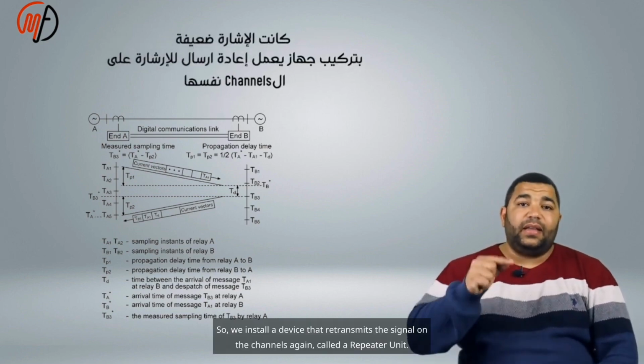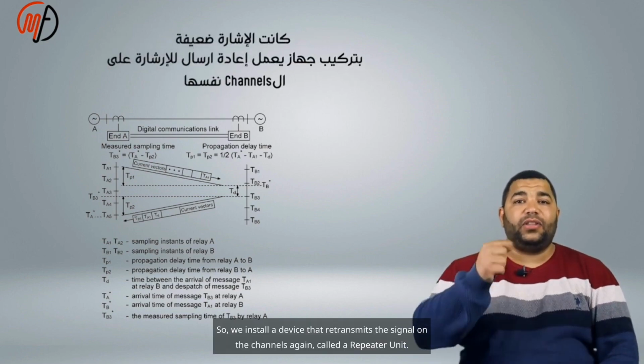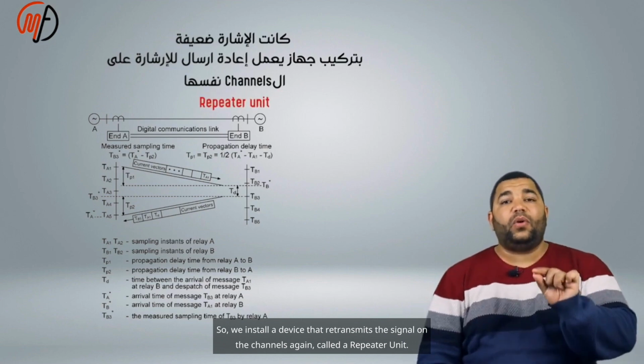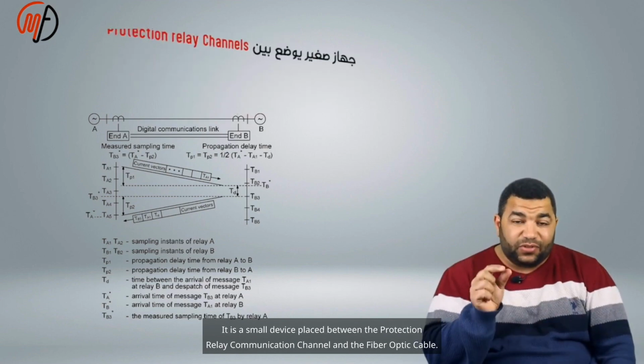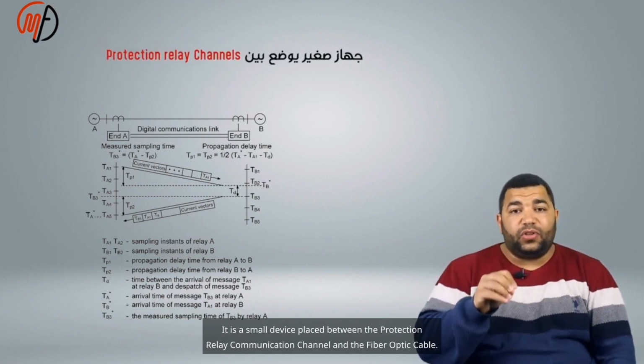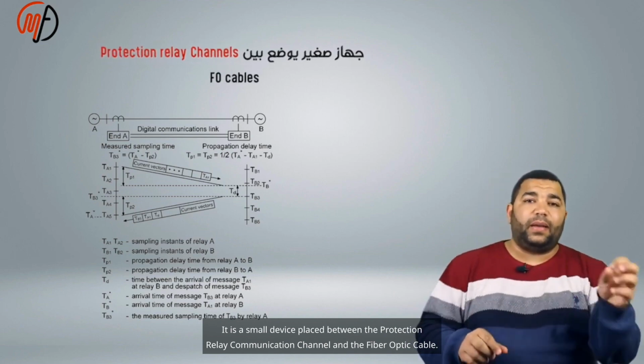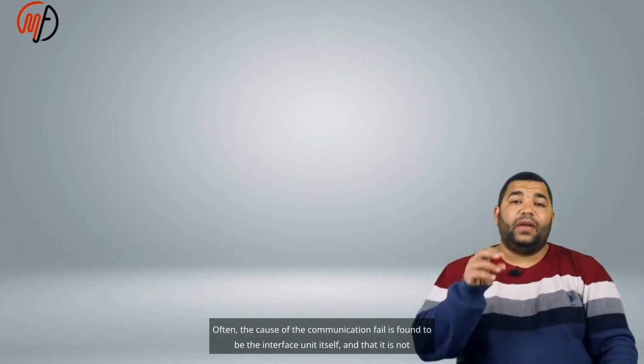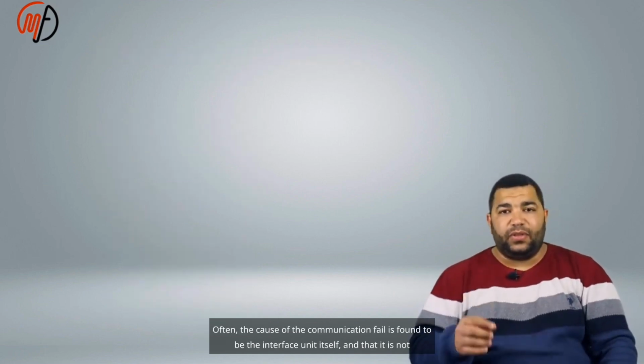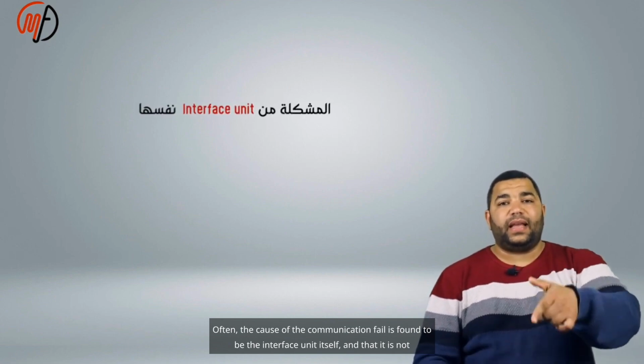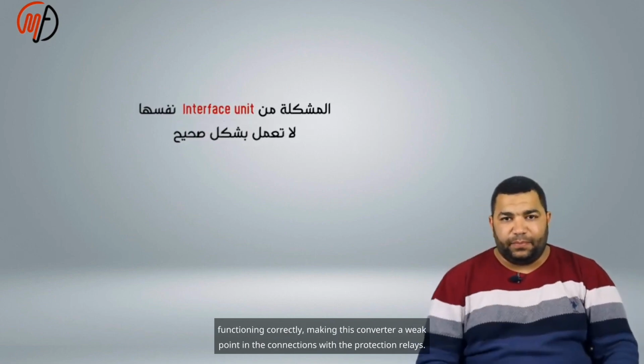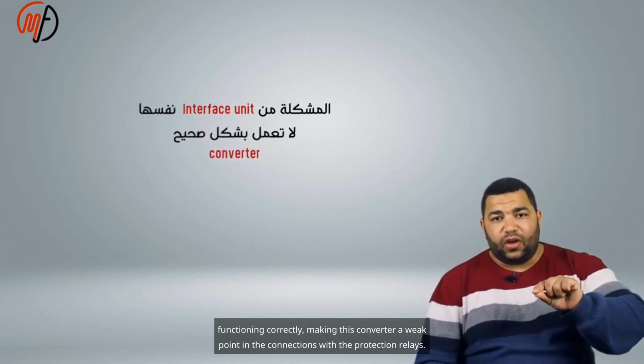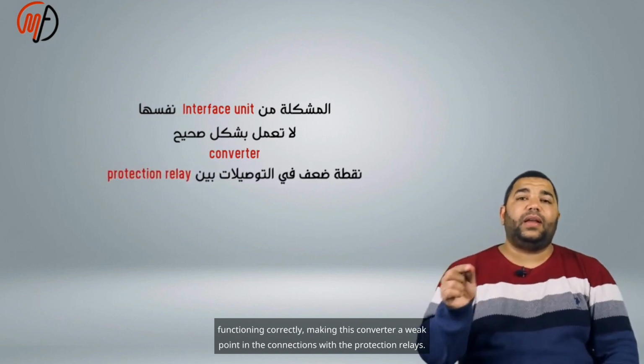So, we install a device that retransmits the signal on the channels again, called a repeater unit. It is a small device placed between the protection relay communication channel and the fiber optic cable. Often, the cause of the communication fail is found to be the interface unit itself and that it is not functioning correctly, making this converter a weak point in the connections with the protection relays.